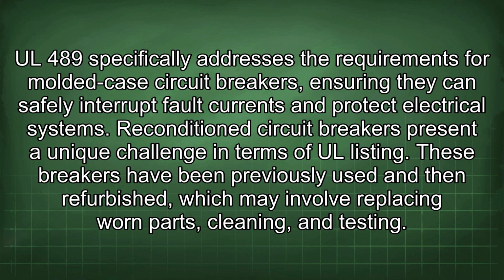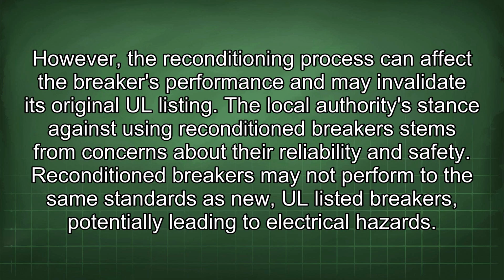Reconditioned circuit breakers present a unique challenge in terms of UL listing. These breakers have been previously used and then refurbished, which may involve replacing worn parts, cleaning, and testing. However, the reconditioning process can affect the breaker's performance and may invalidate its original UL listing.